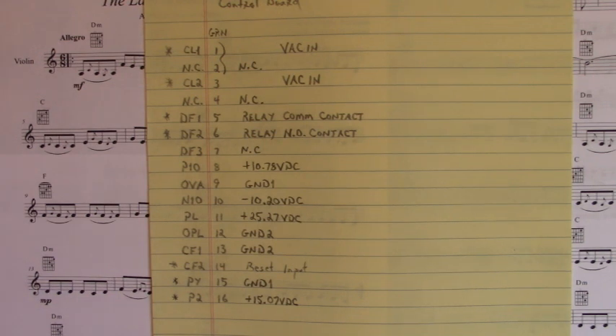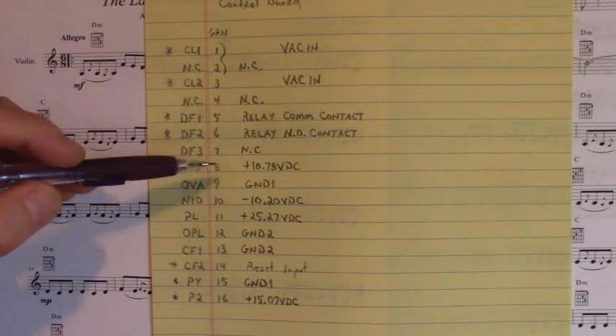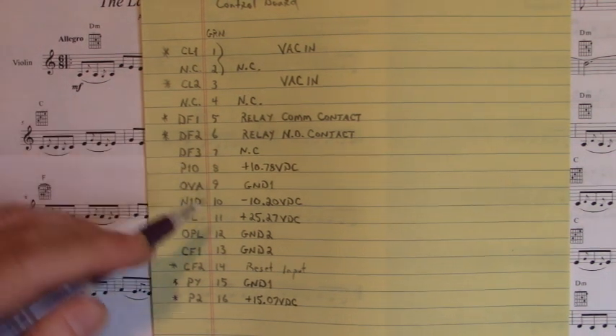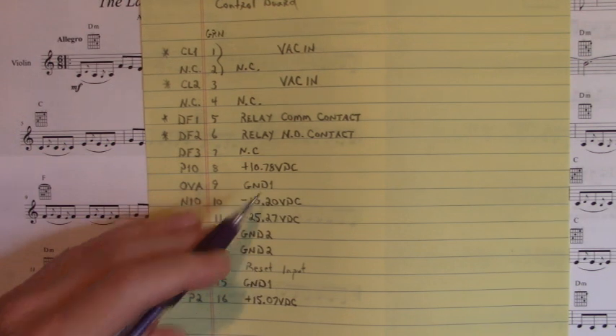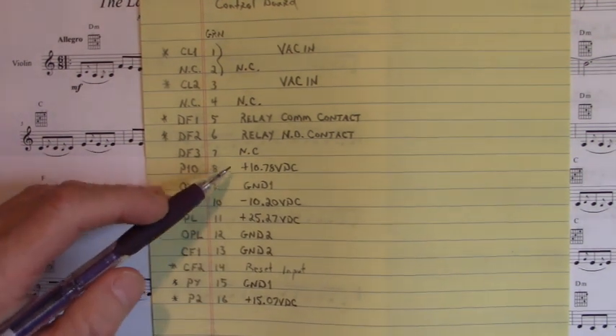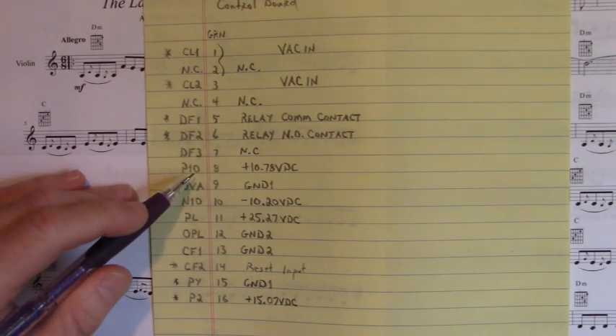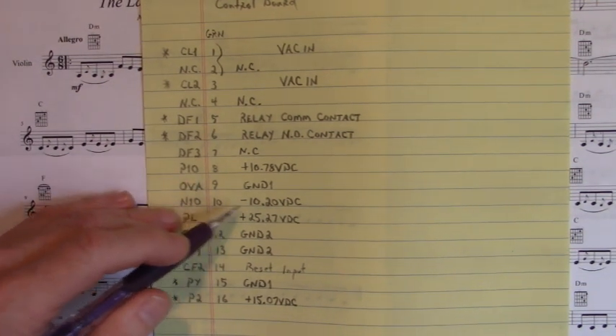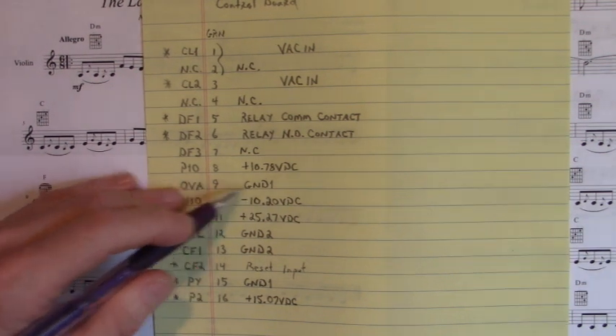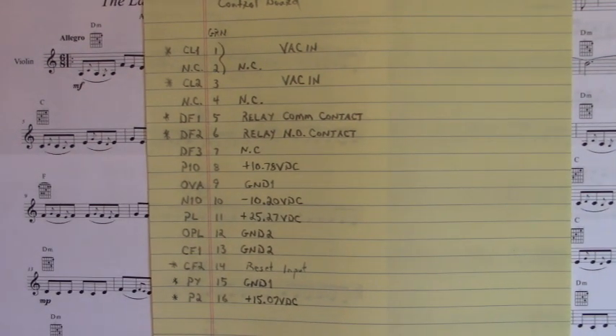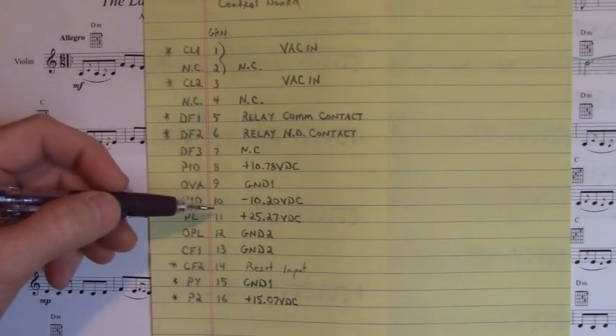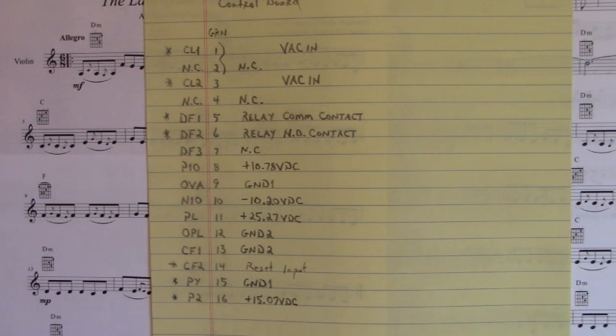Now here is a little bit strange. We have a power supply of plus 10 volts and ground. I called it ground 1 because we have ground 2 down here. So we have plus 10 volts on pin 8 and minus 10 volts on pin 10, reference to pin 9, this ground. Now whenever I see plus and minus 10 volts and ground, I think this is a speed reference for a potentiometer. But now why would you put that on the bus power supply? Why not on the drive? Really odd.